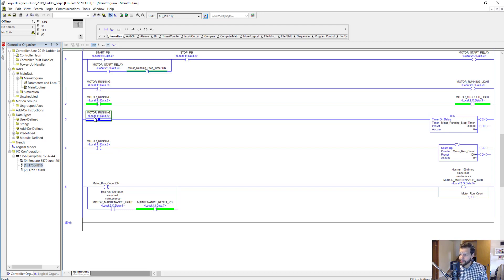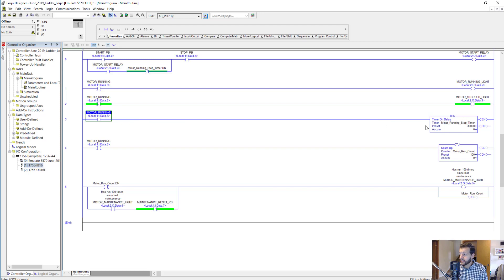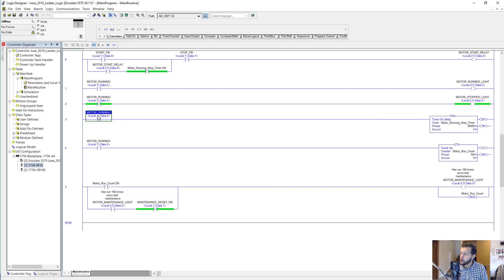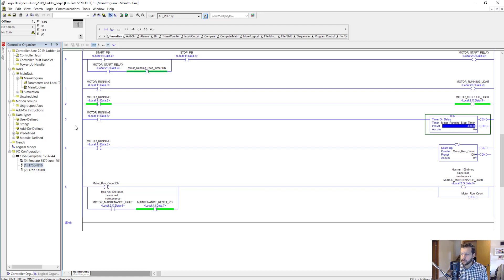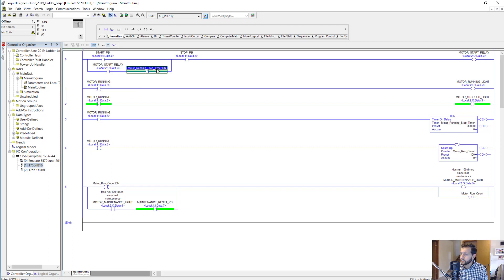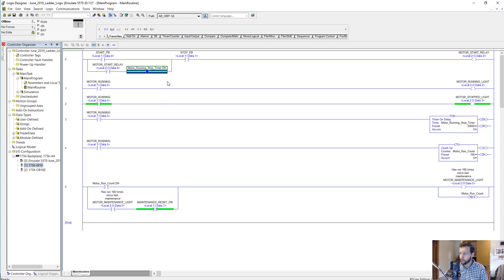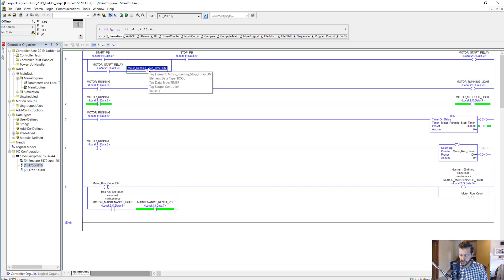Okay, so rung three we've got our motor running input again starting a TON timer, which means it turns on when the input is true. It's set for 30,000, which is 30,000 milliseconds or 30 seconds. So after the motor has run for 30 seconds, this done bit will become true, which will make this XIO open and interrupt the motor start relay as we discussed before.